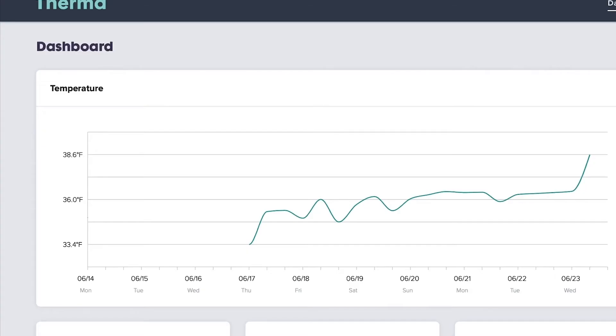Let's take a look at five real-life examples to learn how to draw actionable conclusions that may occur throughout restaurant operations. Here, we notice a gradual upward trend in temperature for this unit since deployment, resulting in an increase in the average temperature of nearly five degrees Fahrenheit. In this situation, we recommend turning down the temperature of this unit to see if this resolves the increase in temperature. A slight increase in temperature over a period of time may be an early indicator that this unit will require maintenance in the near future.